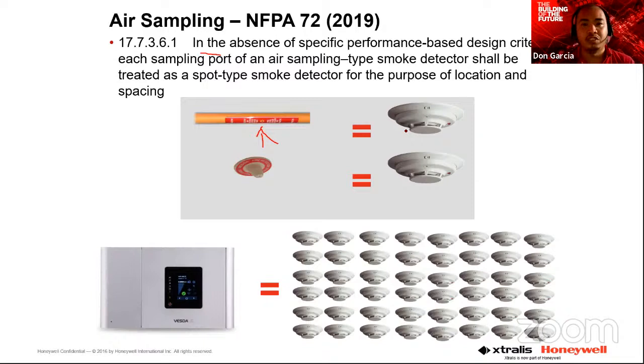Okay. Also, we are using this NFPA standard for the purpose of location and spacing. As we know in the NFPA standard, a spot detector from the next spot detector must be 9.1 meters or less. So that is where we also use the hole-to-hole spacing. So with the VESDA detector, in one pipe, if you put multiple holes, you can have multiple smoke detectors in one pipe. So that is the use of the VESDA system or air sampling system.